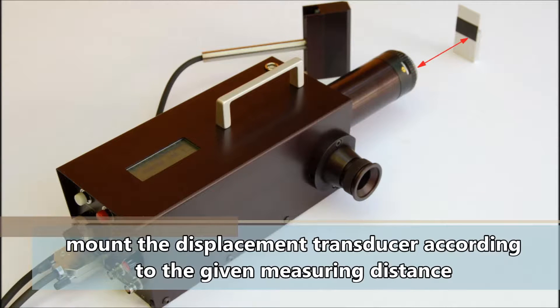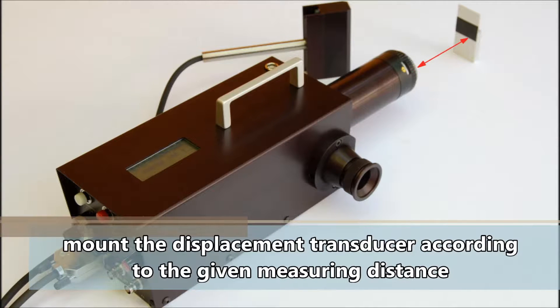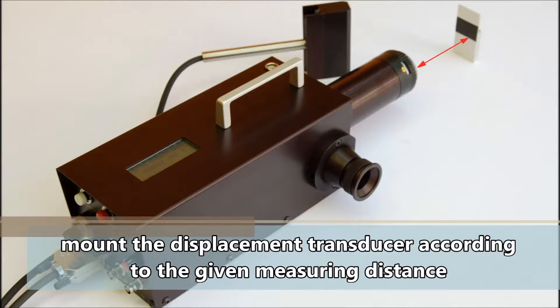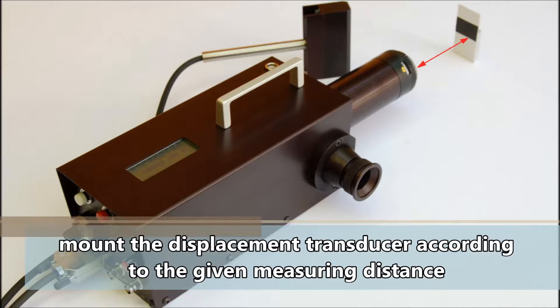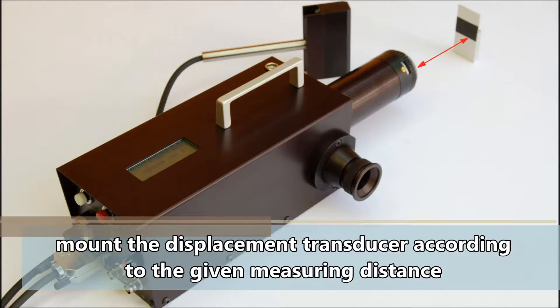The displacement transducer is mounted in front of the object of measurement, which is supplied with a black and white edge. Make sure to comply with a given measuring distance.